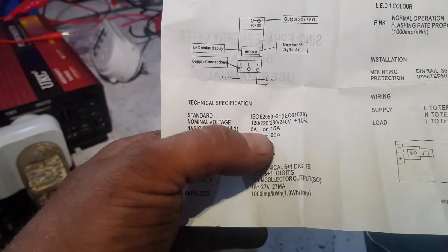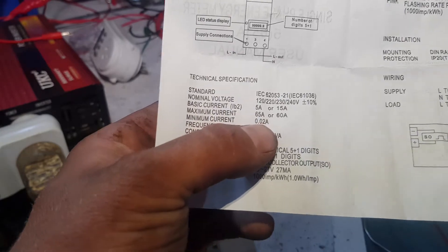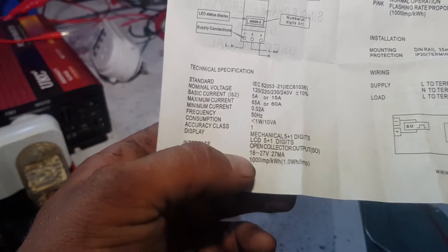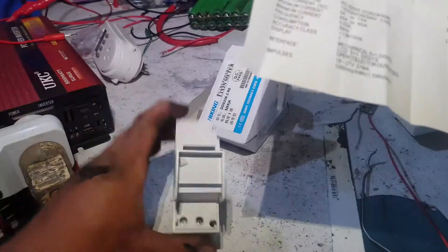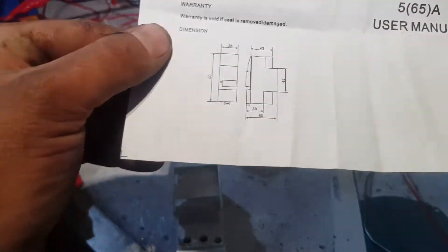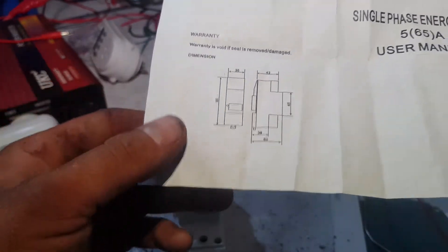It says basic current 5 amps or 15 amps. Maximum current 65 amps, minimum current 0.02 amps - that's what I wanted to know, I wanted to know when it will start actually picking up. Consumption display: 5 plus 1 digits. One watt hour per little red light flash.